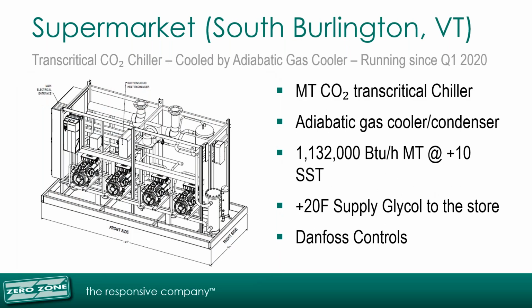In Vermont, this retailer wanted to reduce their overall refrigerant charge and exposure. They've been using glycol to refrigerate the medium temperature cases and walk-in coolers, and they wanted to continue with that design. To reduce their refrigerant footprint, they decided to use CO2 on the high side of the chiller in lieu of R404A or R448A. Ultimately, they removed all or almost all of the HFCs from the store.